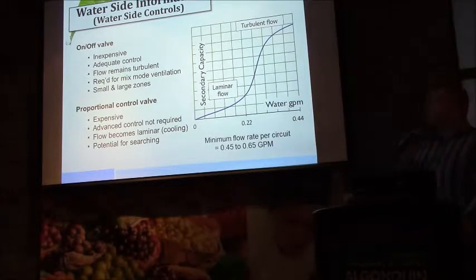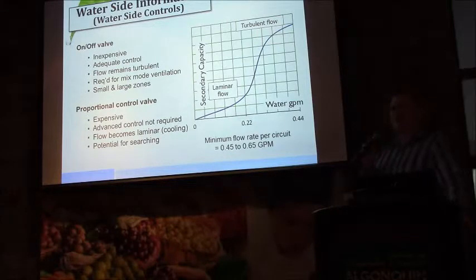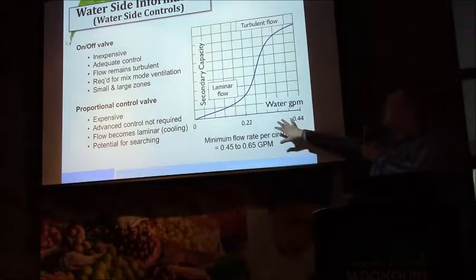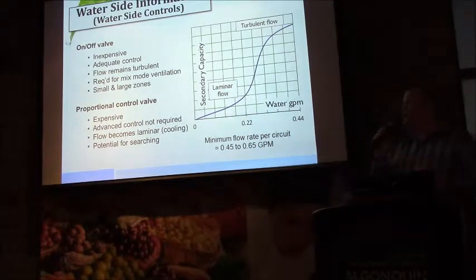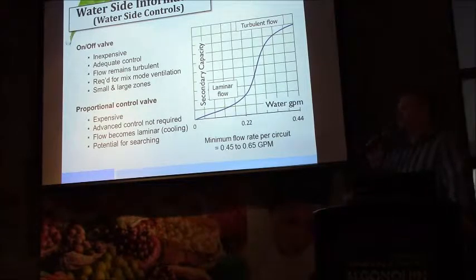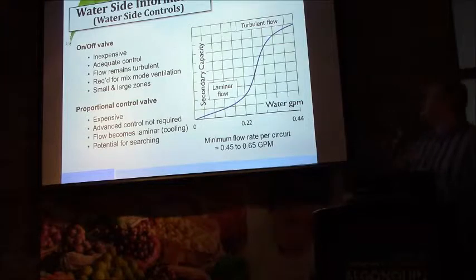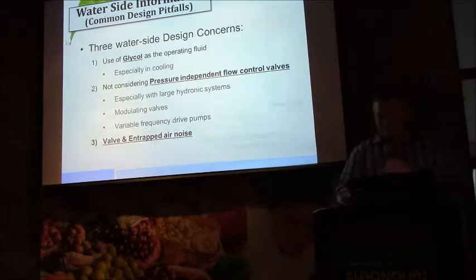Modulating the water flow is an issue because we're already at the lower limit of what we would distribute to a half inch tube. You can imagine that a water control valve for a half a GPM or 0.65 GPM into a typical 2x4 coil is going to be a needle valve. It's going to be prone to failure because any debris in the piping distribution system is going to get caught up in that needle valve, and it'll be expensive. Modulating a half a GPM seems reasonably senseless for the benefit.